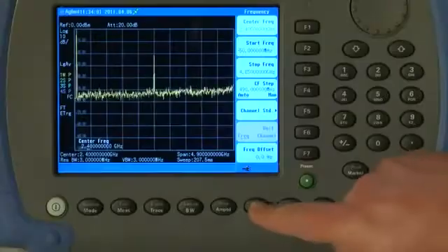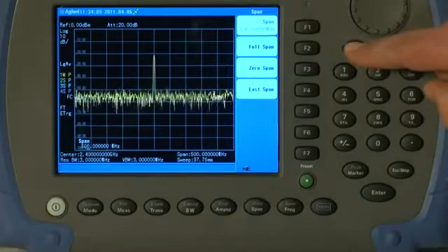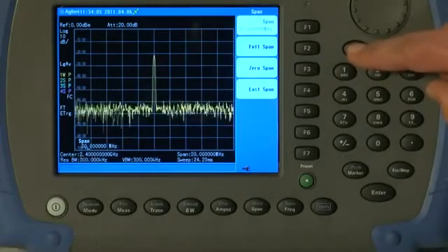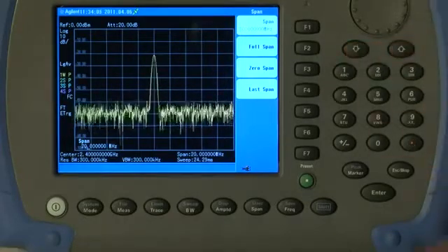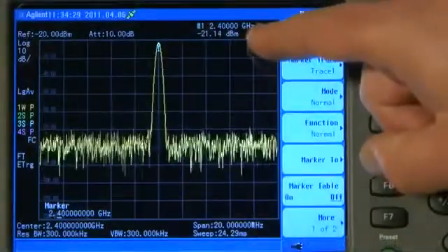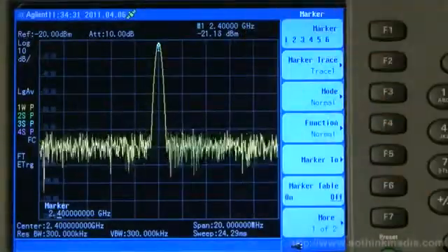I can then press the Span button and using the down arrow keys, I can zoom in on the signal and I can press the Amplitude button and change the reference level, again using the arrow keys to bring the signal to the top of the Graticule and then I can press the Marker button and I can read the amplitude value of the signal, approximately minus 20 dBm.